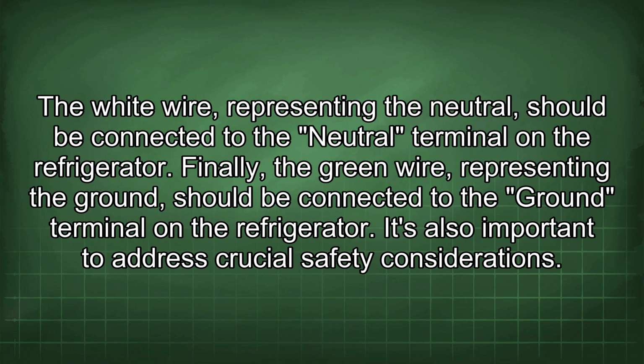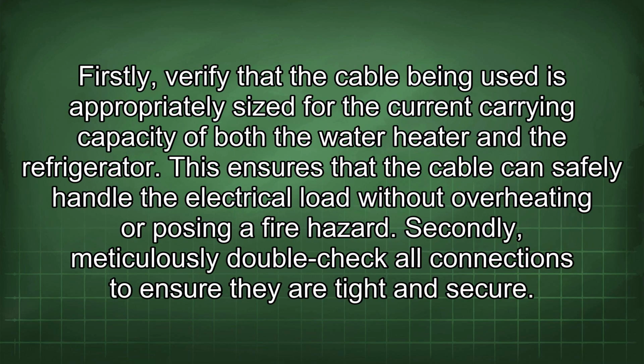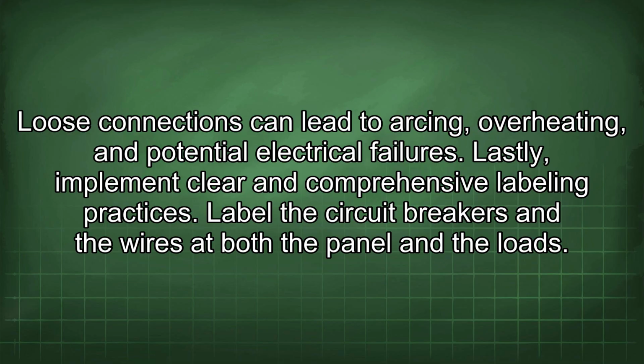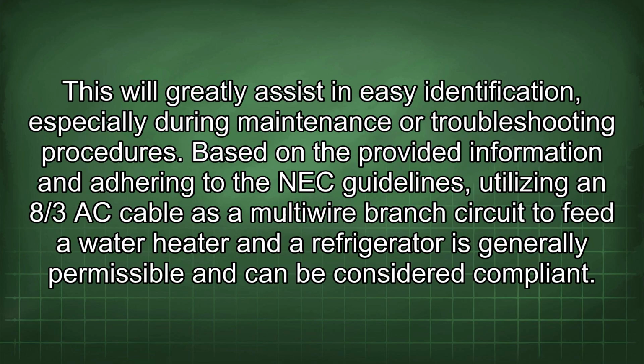It's also important to address crucial safety considerations. Firstly, verify that the cable being used is appropriately sized for the current carrying capacity of both the water heater and the refrigerator. This ensures that the cable can safely handle the electrical load without overheating or posing a fire hazard. Secondly, meticulously double-check all connections to ensure they are tight and secure. Loose connections can lead to arcing, overheating, and potential electrical failures. Lastly, implement clear and comprehensive labeling practices. Label the circuit breakers and the wires at both the panel and the loads. This will greatly assist in easy identification, especially during maintenance or troubleshooting procedures.